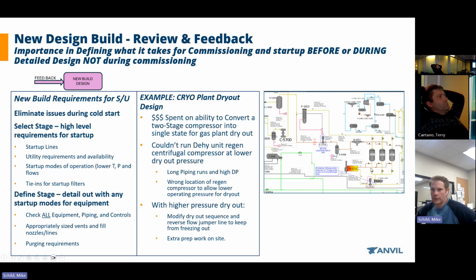We could easily have tied in startup lines. Where this equipment was laid out, we could have had startup lines hooked up right here, with a block valve, providing a suction and a discharge line. So really, it could have just been simple piping mods. It would have been 20 feet of a supply and 20 feet of a return line. It would have been as simple as that if we could have seen that up front.